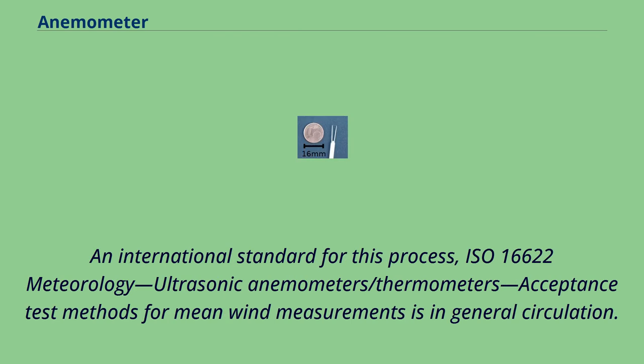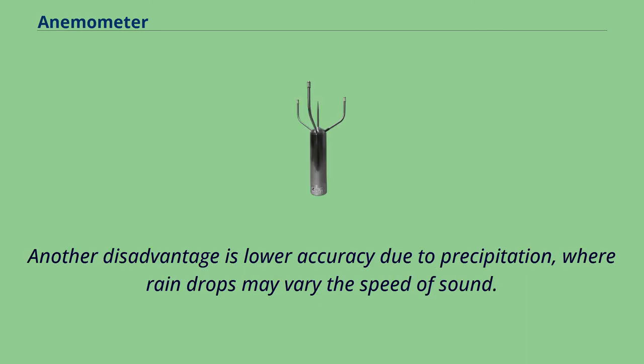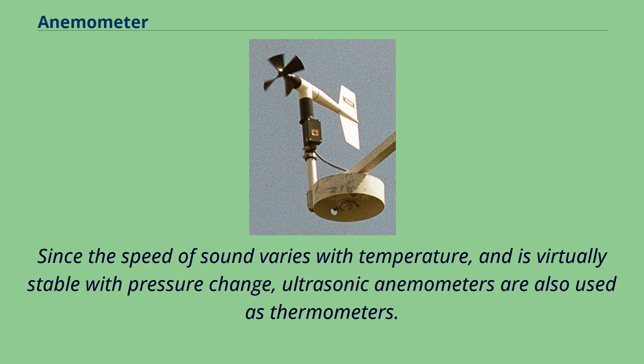An international standard for this process, ISO 16622 Meteorology - Ultrasonic anemometers/thermometers - Acceptance test methods for mean wind measurements is in general circulation. Another disadvantage is lower accuracy due to precipitation, where rain drops may vary the speed of sound. Since the speed of sound varies with temperature, and is virtually stable with pressure change, ultrasonic anemometers are also used as thermometers.